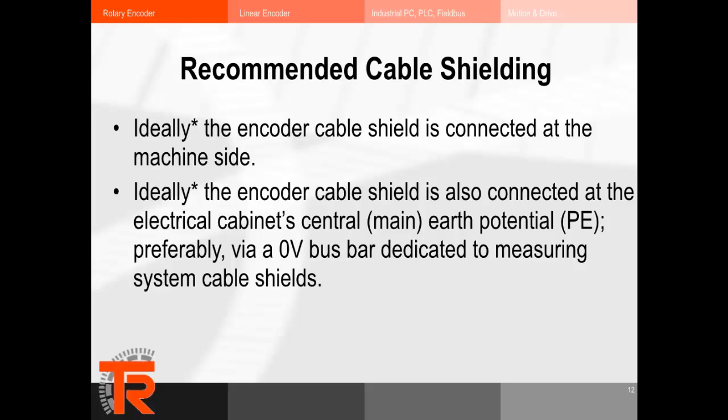For recommended cable shielding, the encoder cable is connected at the machine side and ideally connected to the electrical cabinet's main or earth potential (PE), preferably via a zero-volt busbar dedicated to measuring system cable shields. Our encoder cables have their shield connected to the connector housing whenever possible, keeping the shield as close to the encoder housing as possible. Some manufacturers use a shield pin in the connector on the encoder housing — we don't recommend that, as it routes noise into the encoder housing. You want to keep the electronic circuit boards inside isolated from noise as much as possible.